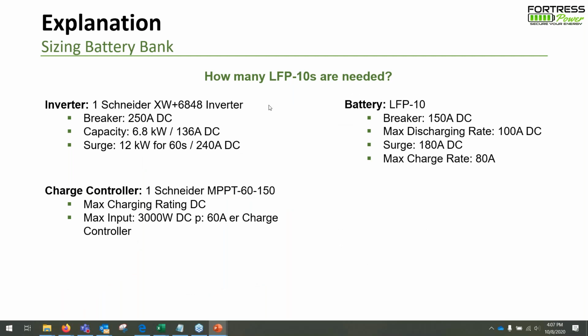So here's an explanation of sizing the battery bank. I know many of you have already seen this, but I will go over it one more time because I think it's very important. The XW Plus inverter 6848 has a breaker of 250 amps, capacity of 6.8 kilowatts, and it's able to demand from the battery 136 or 140 amps. The surge is pretty high as well, 240 amps. We won't look into the charge controller right now, we'll just look at the inverter.